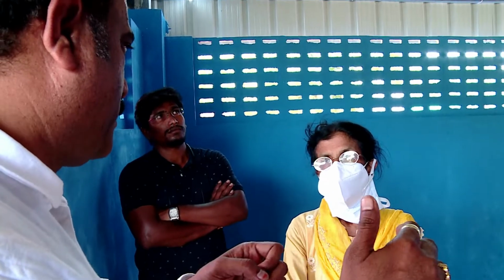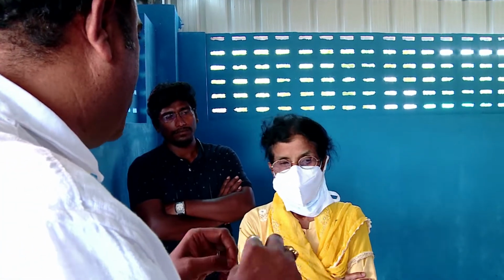That we are scrubbing by using the sodium hydroxide solution, where we are using 0.2 normality sodium hydroxide solution. If any chloride fumes form, it will form as sodium chloride. So again, it has to be monitored. The pH is continuously monitored, so we are always maintaining a pH of 10. Whenever it drops, a top-up of sodium hydroxide will be done, maintaining always alkali in the scrubbing solution.